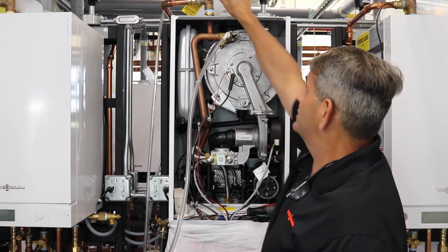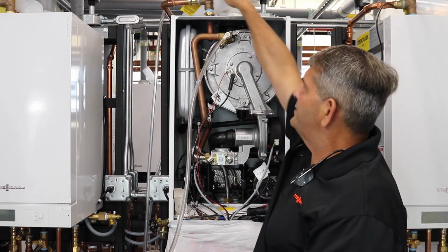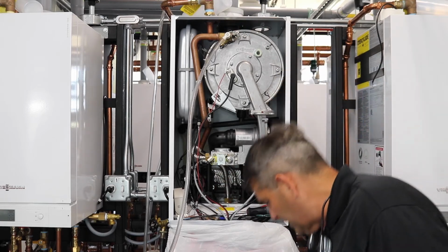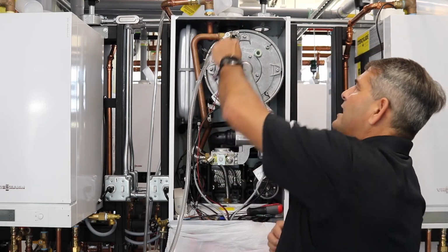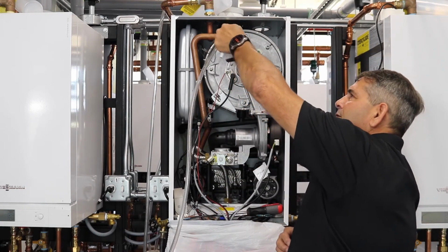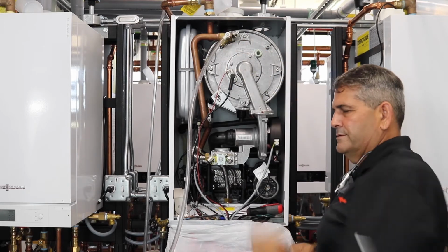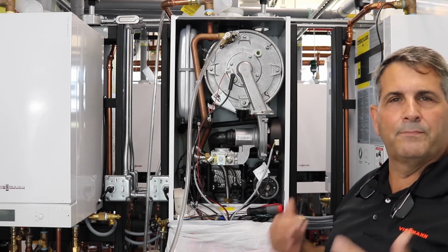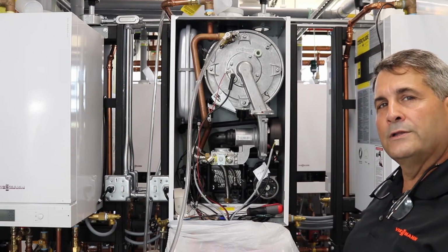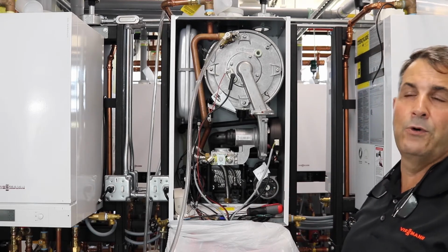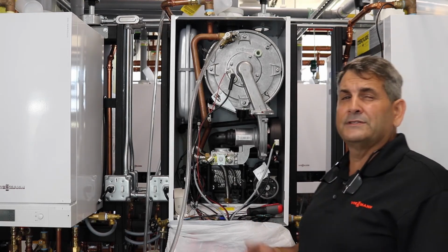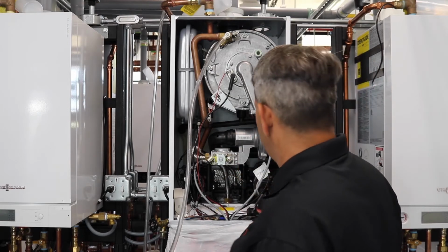The other thing you can do is open up your relief valve to induce air in there, or open up your bleeder here as well to get some air inside the top of the boiler to let it drain. It doesn't take long at all. And remember about the purge mode and your coding level. It's your very first code that will help you purge the boiler if you do happen to get all the water out. I think for this scenario though, we'll be lucky enough not to get too much water.